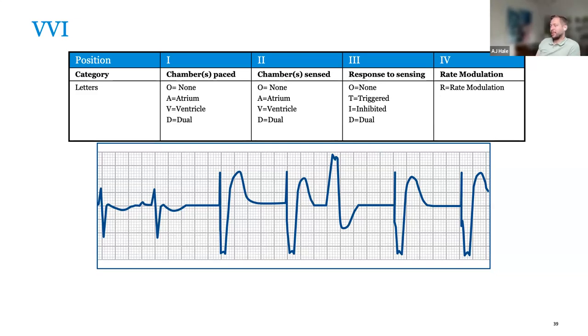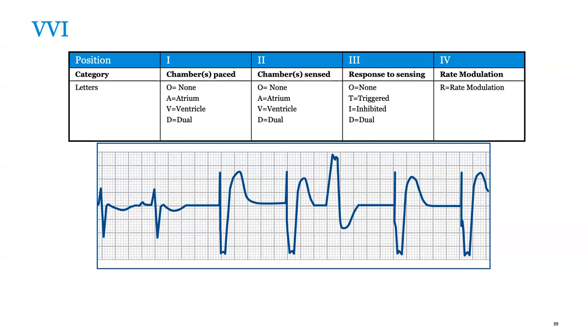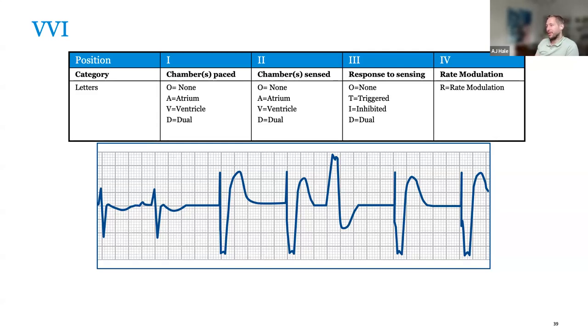Abbott has something similar where you can program the max trigger rate. Boston Scientific has one as well. Medtronic's may be a little more complex and robust for this kind of algorithm. What typically happens is one device company comes up with a cool algorithm and everyone else rolls out their own version within their legal ability — so most device companies will have something similar in their biventricular devices.